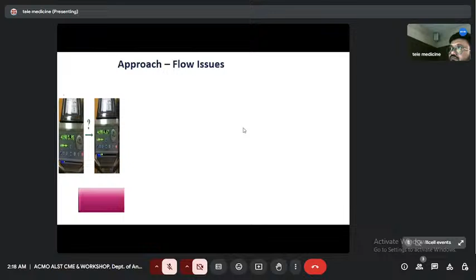Same RPM, flow will be low. So again, first of all, we have to rule out the technical issues. What are the technical issues? We have to correct the flow sensors and all those things. Check the vitals and see for any kinking of the circuit and manage accordingly. And check the circuit pressures P1, P2, P3, and give fluid boluses and increase RPM. Whether we have to accept or not or intervene.